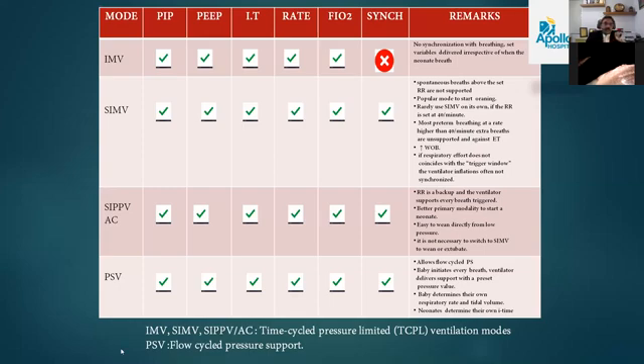The other mode is pressure support ventilation. In pressure support ventilation, as I already told, it is one of the flow termination modes. Whenever the ventilator senses that the baby wants to breathe out, the ventilator will cut off the breath which it is giving, so that the baby can breathe out. So in the bargain, the baby will set its own inspiratory time, and as a result, this has been found to be one of the most physiological types of ventilation for neonates.